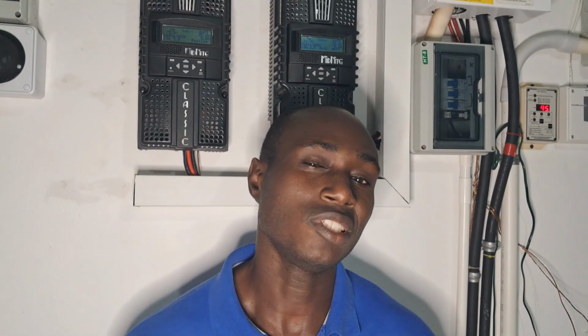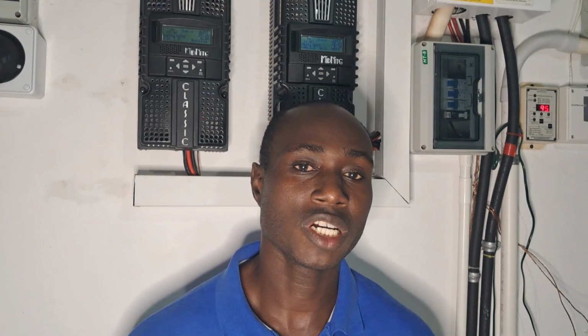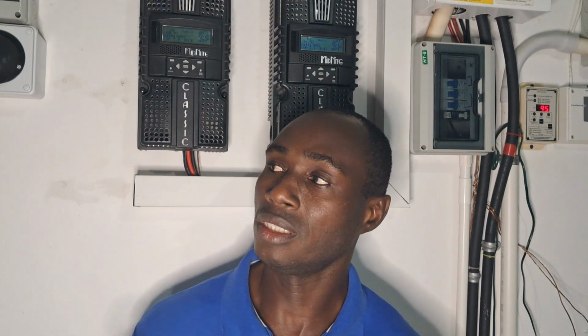This feature requires that a temperature sensor be connected to your Classic, and it's important for both lithium and lead acid batteries. Not so much for lithium, since you should have a BMS with that feature, but if you do, the over temperature protection on your Midnite Classic adds an extra layer of protection so your battery doesn't get too hot, and you know what happens if lithium gets too hot. The same applies to lead acid, so it's important to configure this feature.